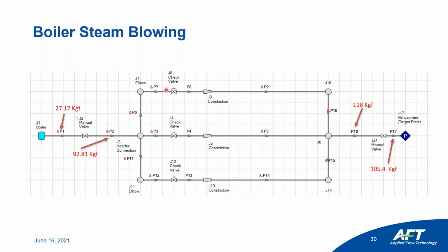As I said, you can as well ask xStream to calculate the forces for all the rest of the pipes, so you can design the guides, anchors and stops properly to handle the forces generated by the dynamic loads.